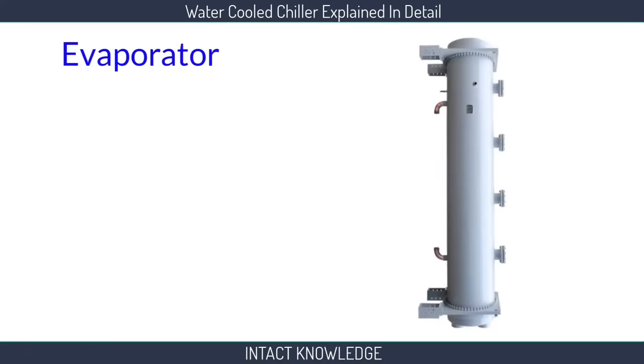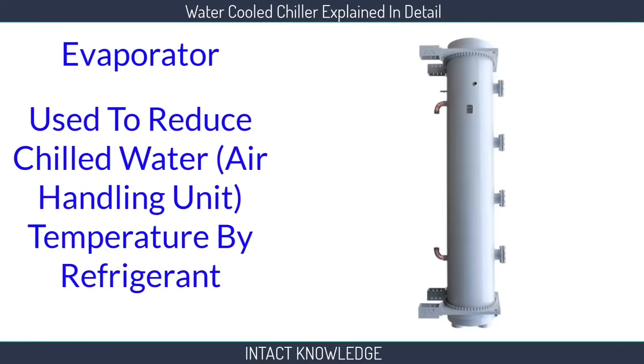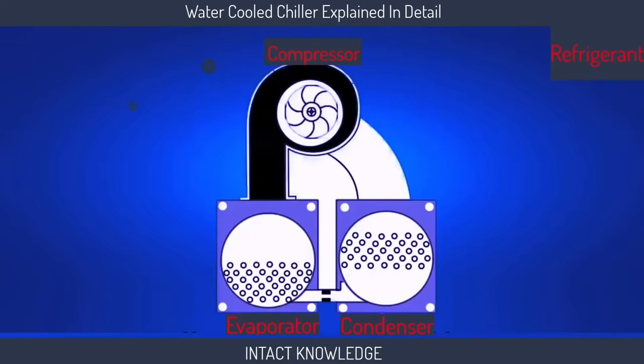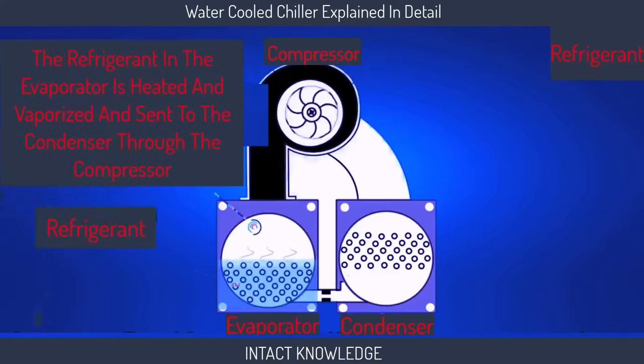Last, evaporator. The evaporator reduces the temperature of the water coming from the AHU with the help of refrigerant and sends it back to the AHU. Now, let's see its working principle. The compressor sends the refrigerant to the condenser from evaporator, which is in the vapor phase.